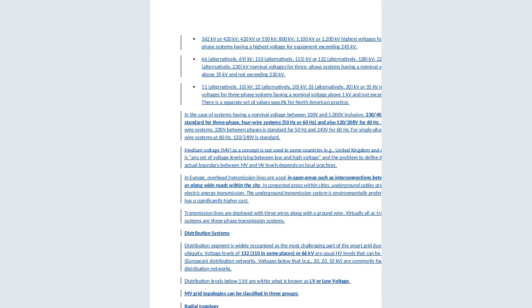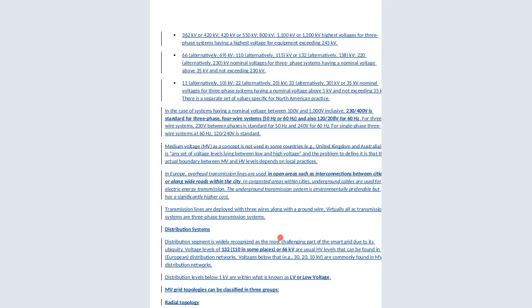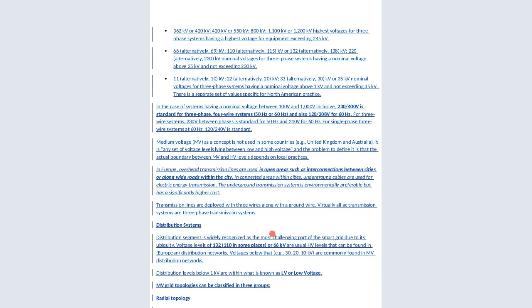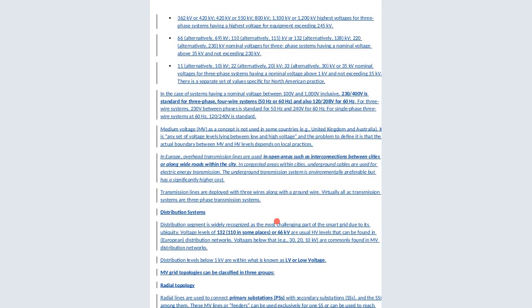So you can see the voltages and the ratings where the transmission takes place. We normally have 66 kilovolts, 33 kilovolts. The 132, we said, is the transmission voltage. In case the systems have a nominal voltage between 100 and 1000 volts inclusive, that is standard for 3-phase, 4-wire systems, at a frequency of 50 hertz or 60. Normally the standard frequency for our country, Kenya, is 50 hertz, and 120/208 for 60.